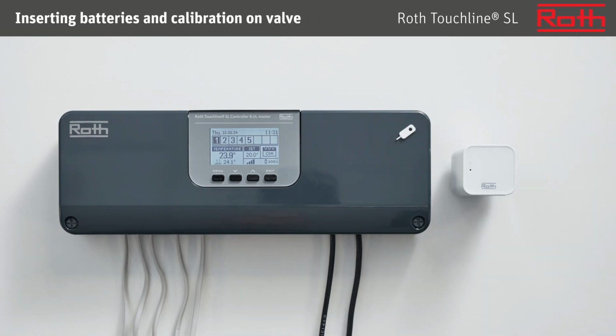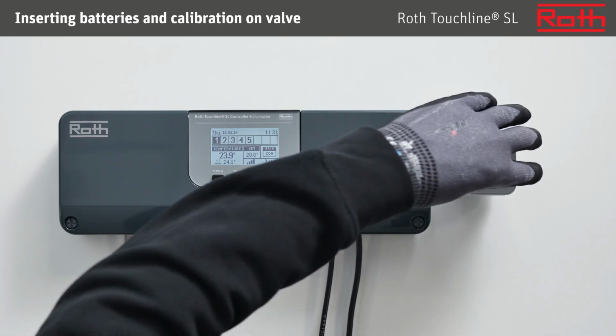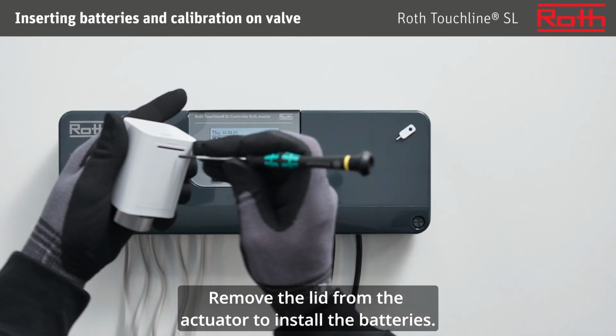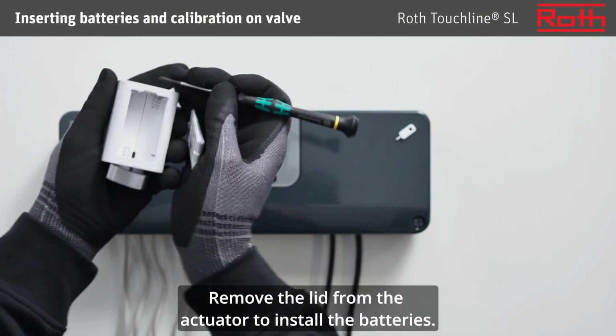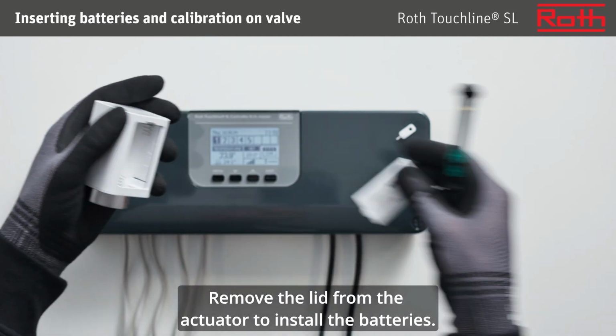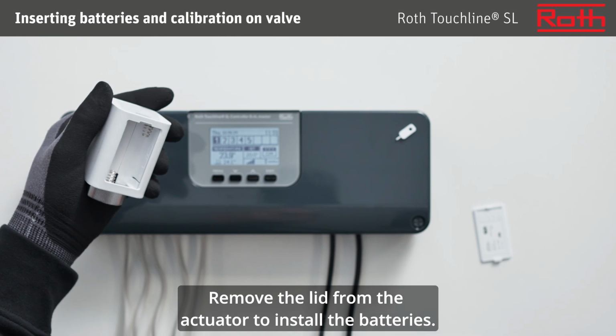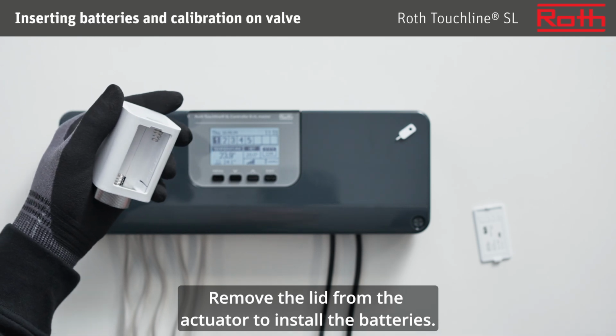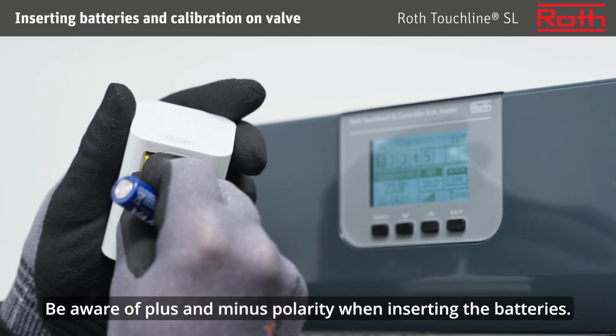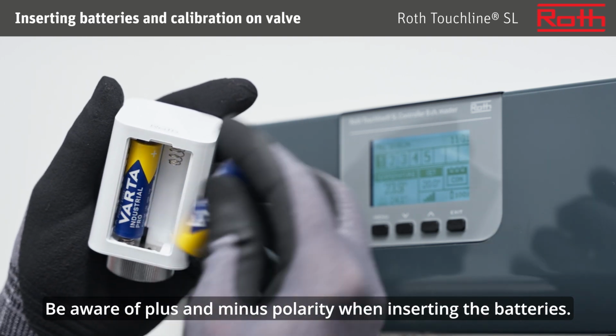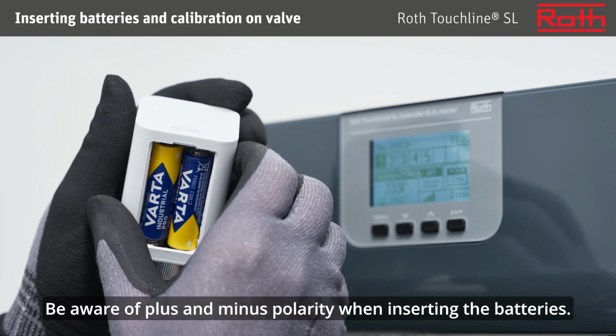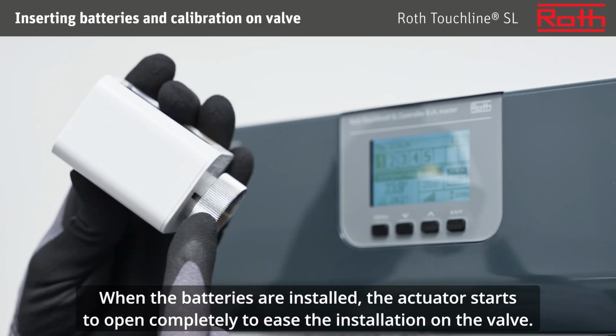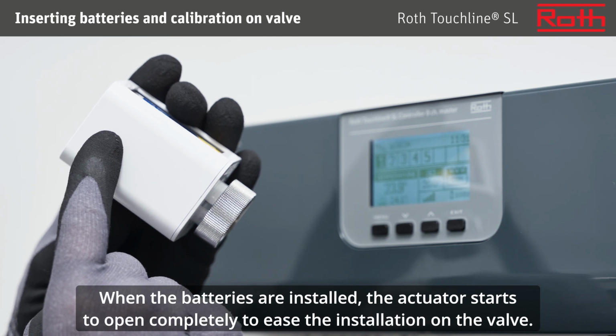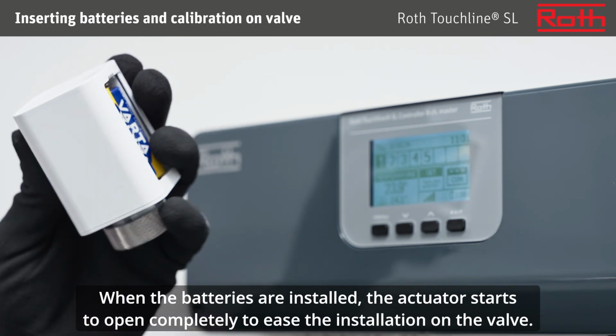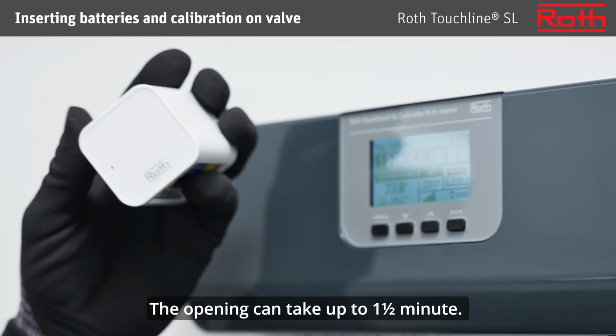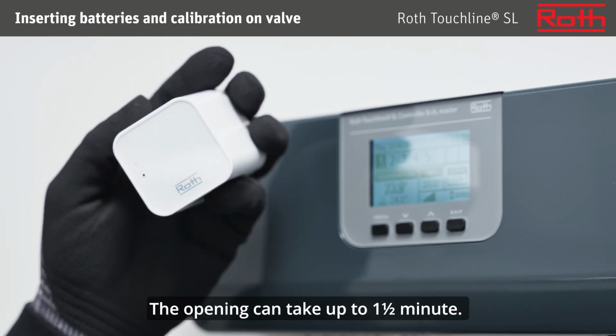Inserting batteries in radiator actuator and calibration on valve. Remove the lid from the actuator to install the batteries. Be aware of plus and minus polarity when inserting the batteries. When the batteries are installed, the actuator starts to open completely to ease the installation on the valve. The opening can take up to 1.5 minutes.